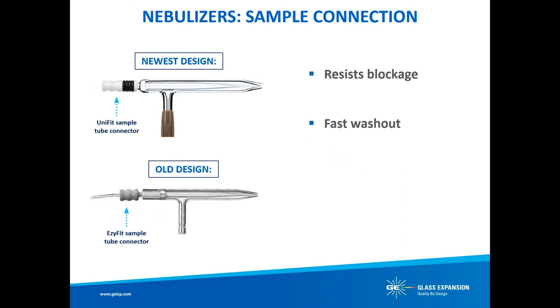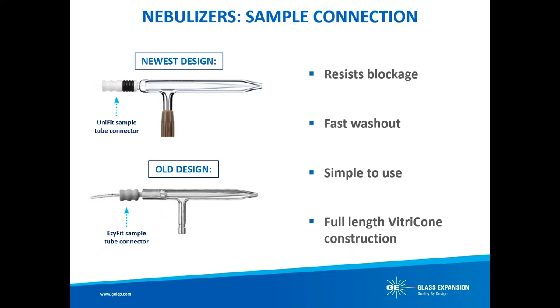The U-Series provides the fastest washout. Since there is zero dead volume — meaning there is nowhere for sample to be trapped — the fastest possible washout and highest sample throughput is achieved. It's the simplest to use: our proprietary Uni-Fit connector slides easily over the sample inlet and creates an excellent seal. It also allows for full-length vitricone construction from end to end, where the sample channel is constructed from a heavy glass capillary machined to very tight tolerances. More information about the vitricone is available in our Nebulizers 101 on-demand webinar.